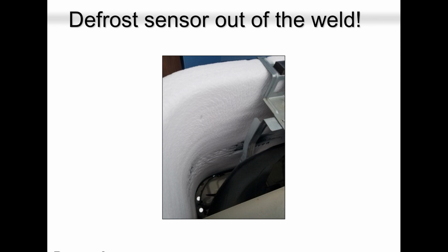This picture here is not a refrigerant issue. This picture here is the sensor. The sensor was out of the well. How it came out, I don't know. The defrost sensor was out of the well and it wasn't sensing cold refrigerant temperatures, and it never brought the system into defrost cycle. And the unit just kept going and going and going.